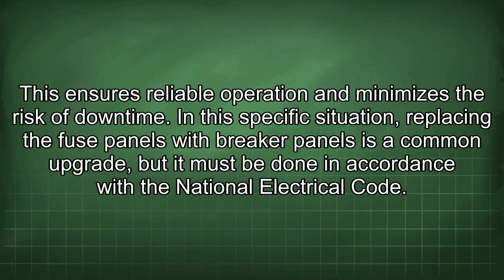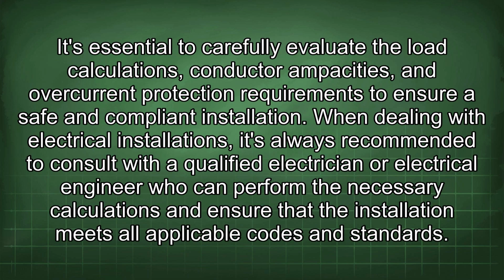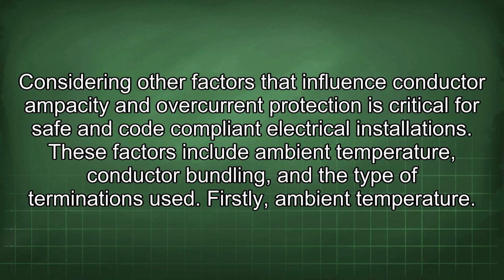In this specific situation, replacing the fuse panels with breaker panels is a common upgrade, but it must be done in accordance with the National Electrical Code. It's essential to carefully evaluate the load calculations, conductor ampacities, and overcurrent protection requirements to ensure a safe and compliant installation. When dealing with electrical installations, it's always recommended to consult with a qualified electrician or electrical engineer who can perform the necessary calculations and ensure that the installation meets all applicable codes and standards. Considering other factors that influence conductor ampacity and overcurrent protection is critical for safe and code-compliant electrical installations. These factors include ambient temperature, conductor bundling, and the type of terminations used.